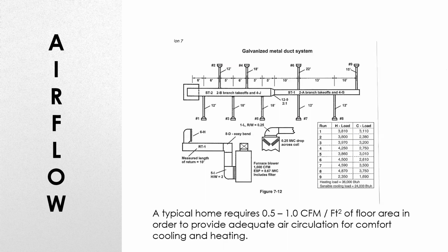You will never get the air circulation in a home to provide comfort, heating, and cooling with that kind of CFM. So when we depart from this typical requirement, then we start having problems. The half CFM probably is a more northern market. The 1 CFM is probably a more southern market because, of course, cooling requires more airflow than heating does. But that's where the big problem comes in. The first real big problem is that once we've done a Manual J, then we do equipment selection, and then we figure out, oh my, we have an airflow issue, and how are we going to deal with that?